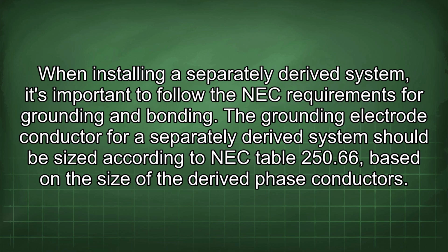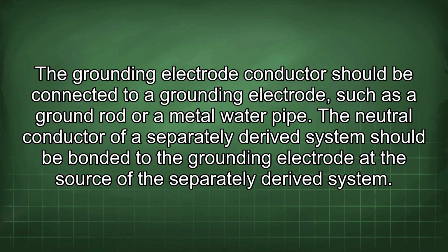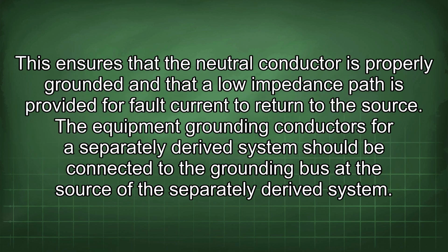The grounding electrode conductor for a separately derived system should be sized according to NEC Table 250.66, based on the size of the derived phase conductors. The grounding electrode conductor should be connected to a grounding electrode, such as a ground rod or a metal water pipe. The neutral conductor of a separately derived system should be bonded to the grounding electrode at the source of the separately derived system. This ensures that the neutral conductor is properly grounded and that a low impedance path is provided for fault current to return to the source.